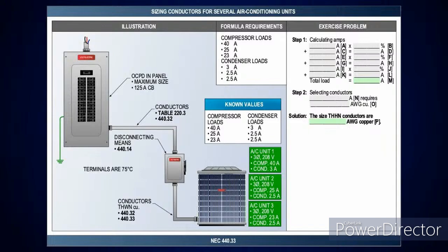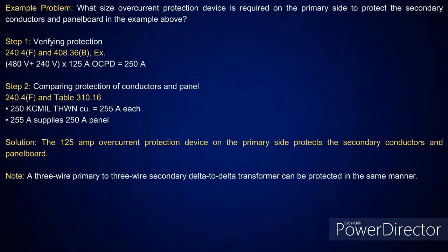So this one, looking at AC units 1, 2, and 3, the largest is the 40 amp. Then everything else is at 100%. Get your total amperage and size your conductor going over there to tap off of that to feed each one of those.